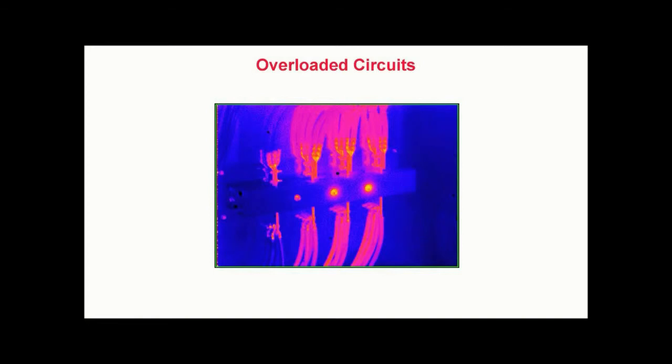Overloaded circuits. This thermogram shows excessive heating caused by an overloaded circuit. Overloads are characterized by uniform but excessive heating throughout the entire length of the conductor.